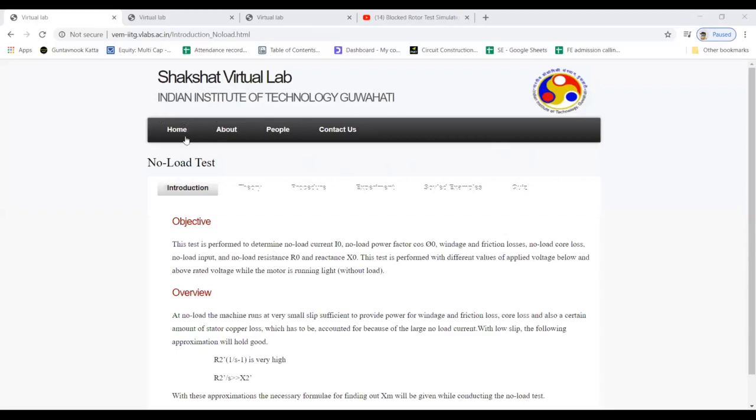You can observe there, this is the home screen, and we are performing the no load test. What is the objective of this? If you press this introduction, you will get this objective.